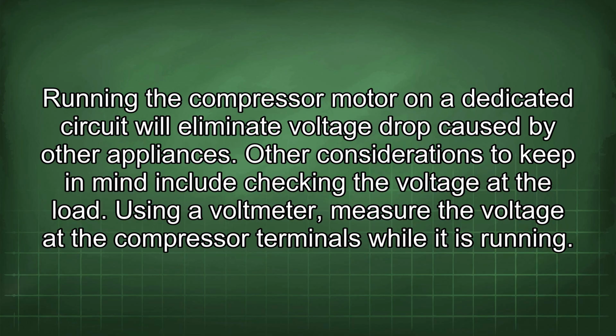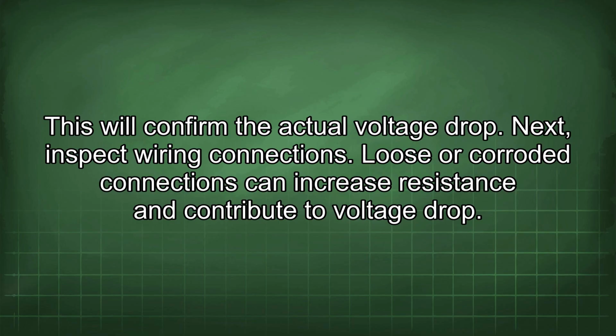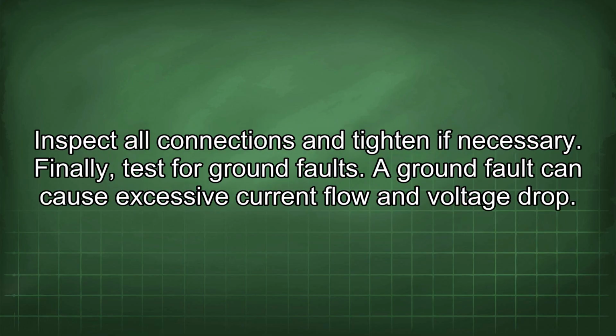Other considerations to keep in mind include checking the voltage at the load. Using a voltmeter, measure the voltage at the compressor terminals while it is running. This will confirm the actual voltage drop. Next, inspect wiring connections. Loose or corroded connections can increase resistance and contribute to voltage drop. Inspect all connections and tighten if necessary.